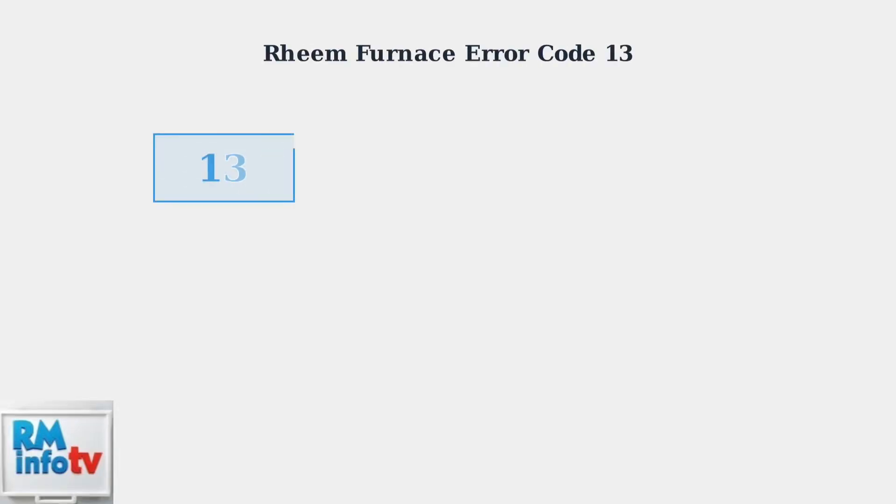Rheem Furnace Error Code 13 indicates a flame lost condition. This means your furnace detected a flame during startup, but that flame unexpectedly went out during operation. When your furnace operates normally, the igniter lights the gas at the burners, creating a steady flame. The flame sensor continuously monitors this flame to ensure safe operation.